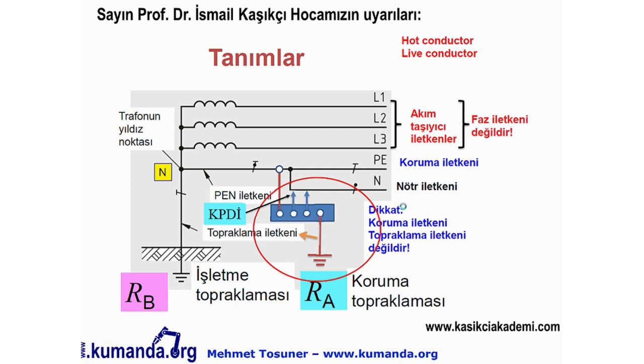Sayın Prof. Dr. İsmail Kaşıkçı hocamızın uyarılarına dikkat etmeye çalışacağım. Bizim faz iletkeni dediğimiz L1, L2, L3 iletkenleri aslında akım taşıyıcı iletkenlerdir; bazı kaynaklarda canlı iletken olarak isimlendirilir. Buradaki koruma iletkeni PE'yi topraklama iletkeni olarak söylememek lazım; bu koruma iletkenidir. Topraklama iletkeni ise trafomuzun yıldız noktasının toprağa bağlantısının yapıldığı kablodur.